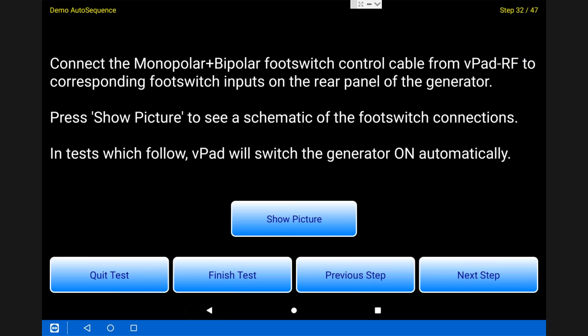So here we're actually indicating an additional function that we gave to this analyzer, being able to utilize the foot switch capability of the generators themselves, allowing for the VPAD RF to turn on and off as needed. The monopolar, both the cut and coagulation modes, as well as bipolar. So if this foot switch is connected, in our next step, all the technician will need to do is make sure that the additional connections for the measurements are done appropriately between the device under test and the VPAD RF. And finally, they'll need to set up the ESU from the front panel display, pressing the precise button, and at the bipolar, setting the power to 70 watts.